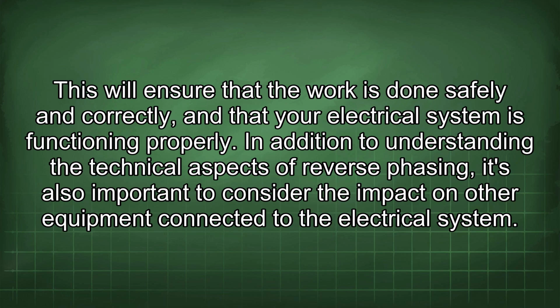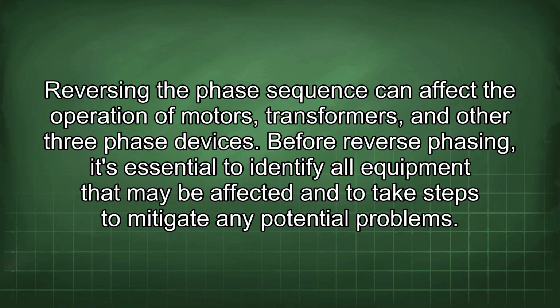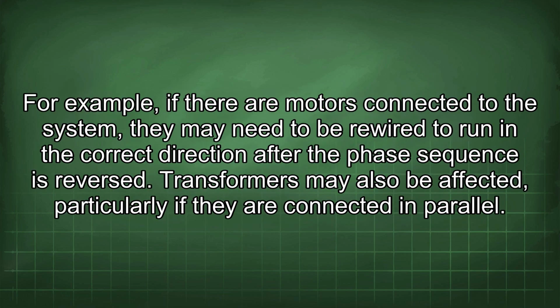In addition to understanding the technical aspects of reverse phasing, it's also important to consider the impact on other equipment connected to the electrical system. Reversing the phase sequence can affect the operation of motors, transformers, and other three-phase devices. Before reverse phasing, it's essential to identify all equipment that may be affected and to take steps to mitigate any potential problems. For example, if there are motors connected to the system, they may need to be rewired to run in the correct direction after the phase sequence is reversed. Transformers may also be affected, particularly if they are connected in parallel.